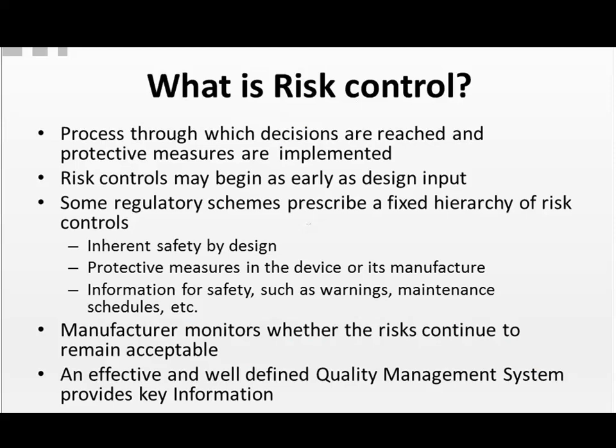Now, some regulatory schemes prescribe a fixed hierarchy of risk controls that should be examined, such as inherent safety by design, which are the protective measures in the device, and information for safety, which includes such things as warnings, maintenance schedules, etc. Now, throughout the life cycle of the device, it's expected that the manufacturer will monitor whether the risks continue to remain acceptable and whether any new hazards or risks are discovered, particularly as devices begin to wear and require maintenance.